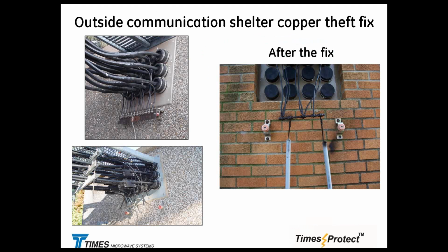Well, take a look. Typical way of doing bulkheads these days. Very traditional way. You've got all the coaxial grounding kits coming. You put coaxial feeders coming in. We've got the grounding kits on the coaxial cables. We dump all that current from the shields, and this is the last point where we can defend ourselves. Right behind that wall, you've got equipment, and we are dumping all that current from the shields of coaxial cables on that one master ground bar, and we put that little fuse.